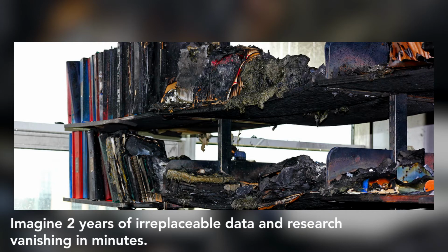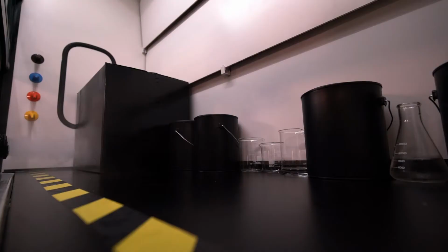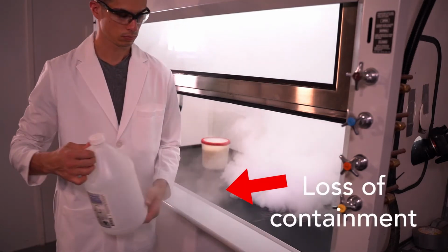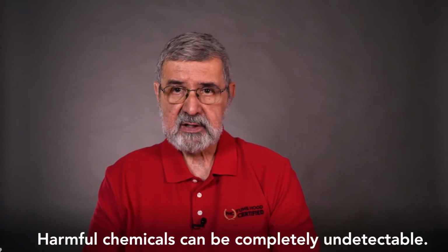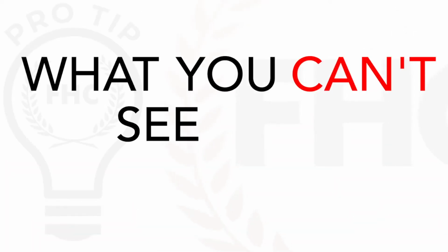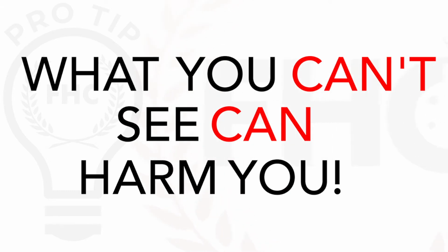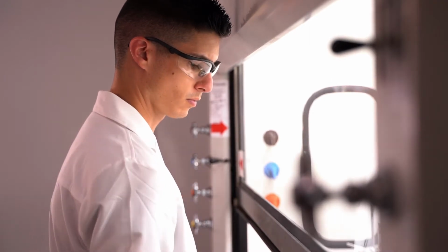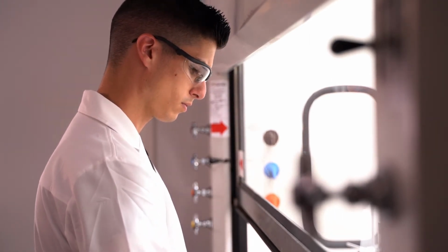Back to your breathing zone. Given the complexity of laboratory ventilation and room conditions, it's nearly impossible for any hood to contain 100% of the time. We can almost guarantee some loss of containment. In many of the demonstration videos, we use smoke or theatrical fog to help you visualize the airflow and show loss of containment. But in real life, the fugitive chemicals are likely to be invisible and maybe even odorless. So what you can't see can harm you. Whether or not you inhale those fugitive chemicals is greatly influenced by the position of the sash in relationship to your breathing zone. Keeping the sash closed as much as reasonable helps protect you.